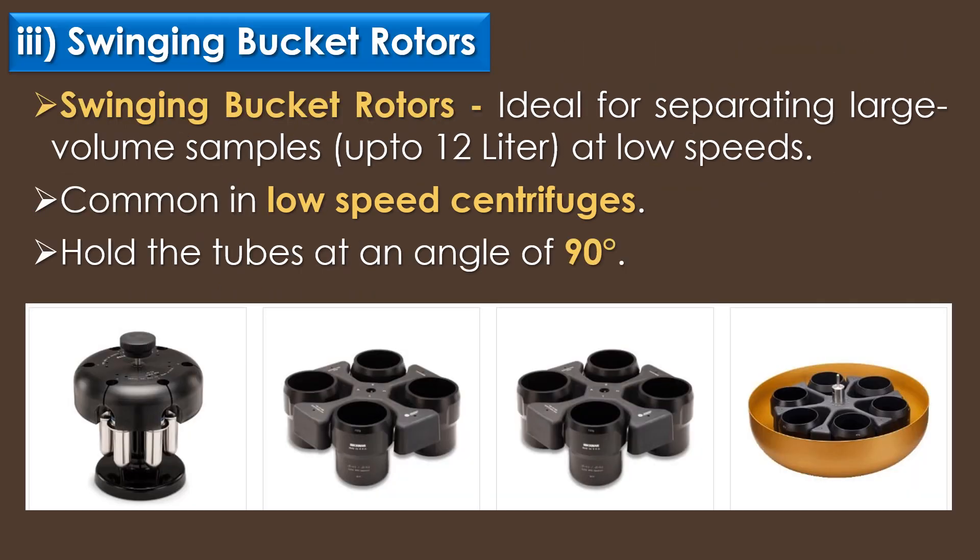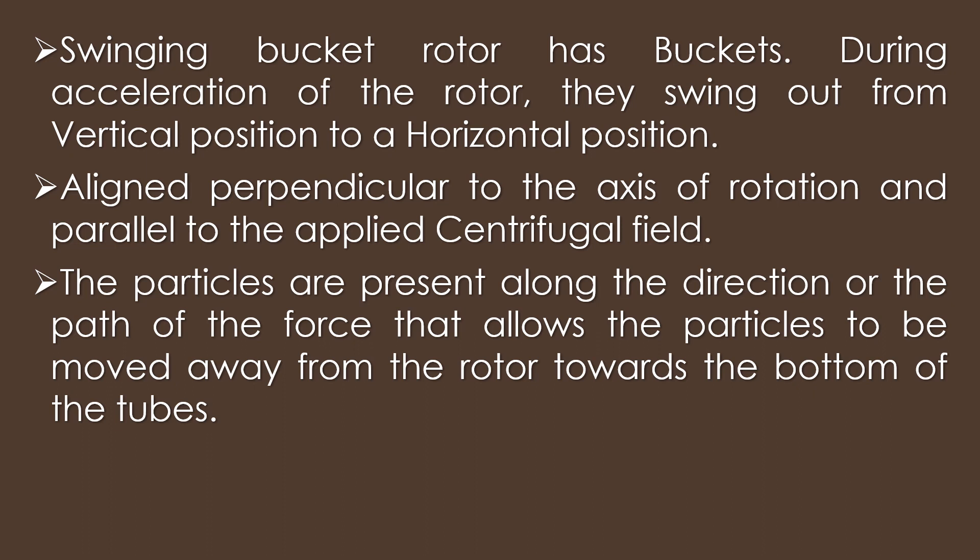The third type of rotor is swinging bucket rotors. Swinging bucket rotors are ideal for separating large volume samples up to 12 litres at low speeds, and are common in low speed centrifuges. Swinging bucket rotors hold the tubes at an angle of 90 degrees as the rotor swings when the process is started. During acceleration of the rotor, the buckets swing out from the vertical position to a horizontal position. Swinging bucket rotors are aligned perpendicular to the axis of rotation and parallel to the applied centrifugal field.